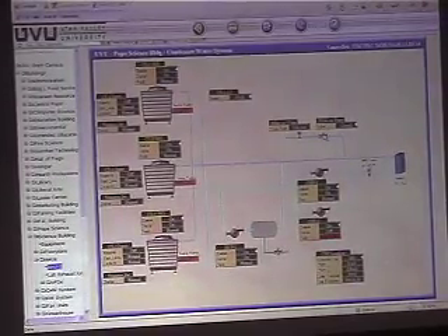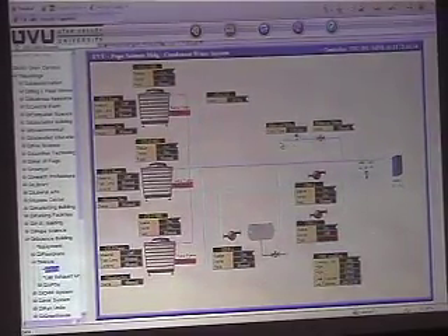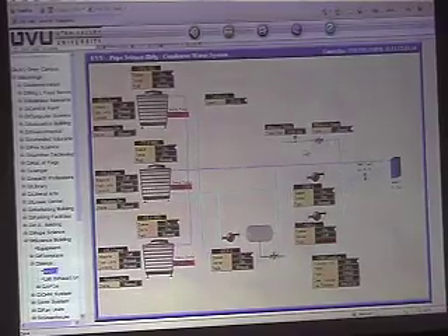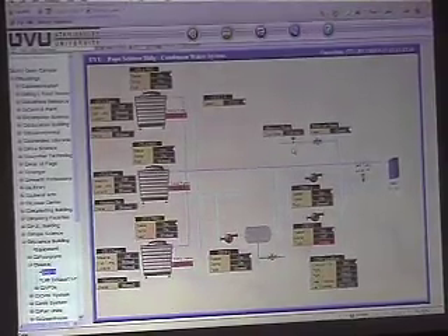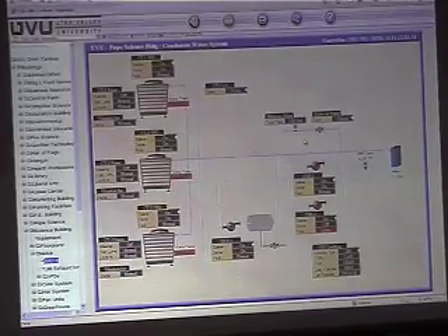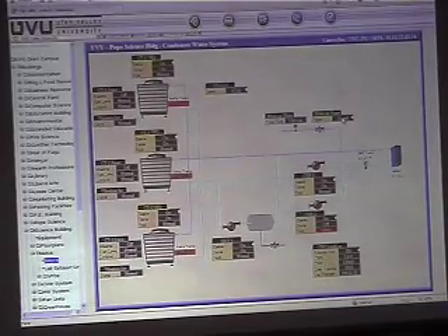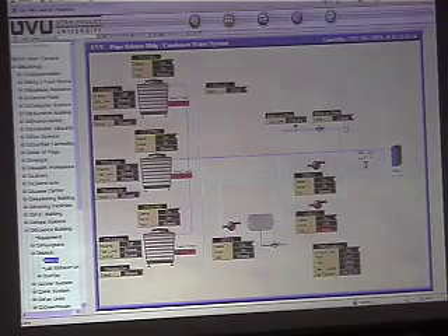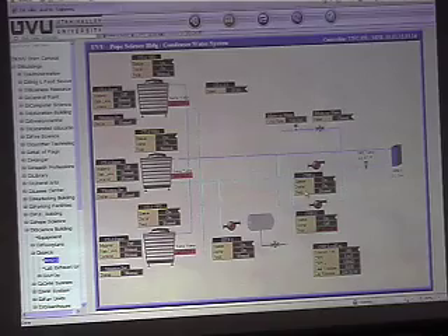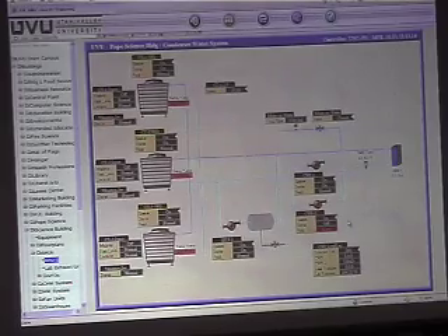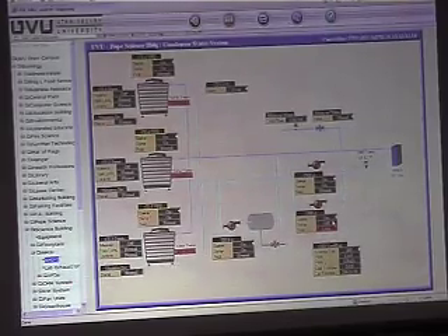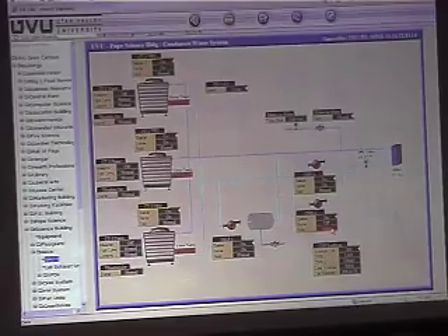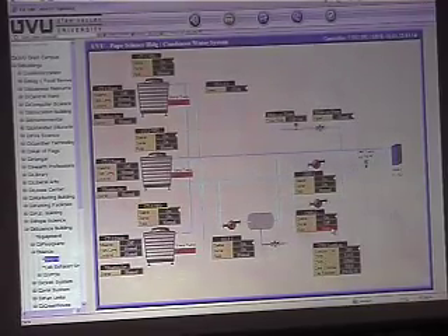We're monitoring the amount of flow on the makeup, and it totalizes here. And then your makeup valve position indication right here. You've got condenser water pumps right here, 1 and 2. They must have this one off up there. I'll have to go see what's going on. But obviously, if the status doesn't match the enable, then you'll get an alarm here showing that something's wrong.